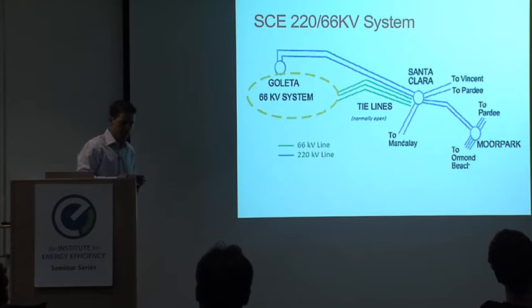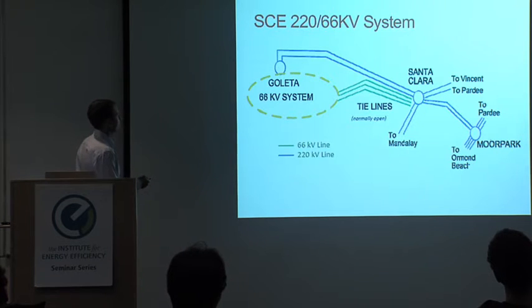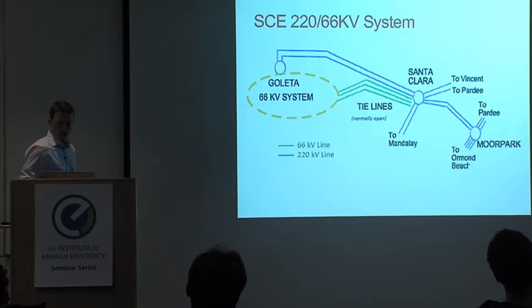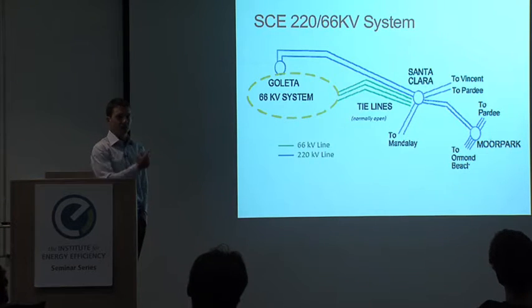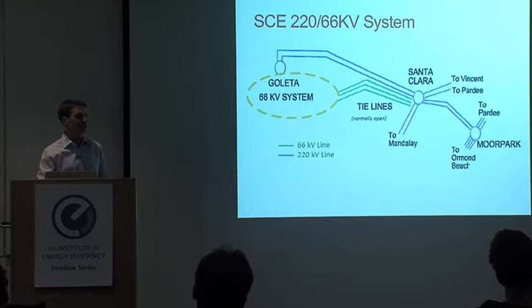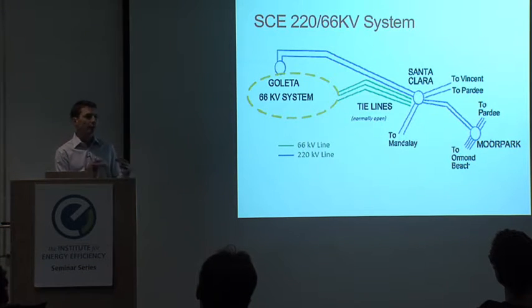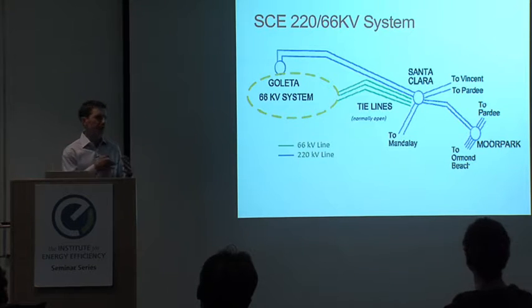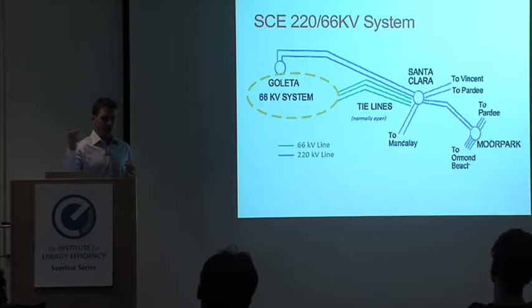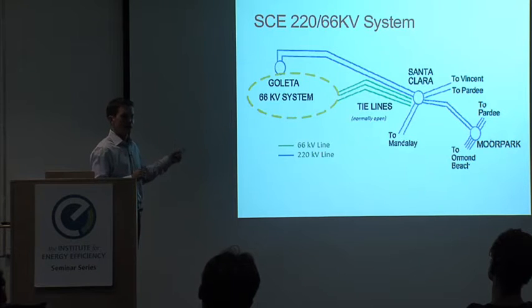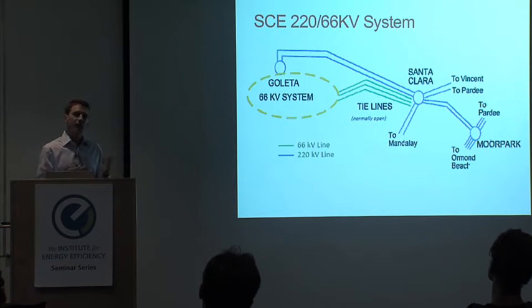This opportunity targets specifically our 66 kV system. This is a conceptual diagram from Edison's GIS layer showing the Santa Clara sub, the 220, and the tie lines. They're looking for 55 megawatts in our area, which is significant—it'll be tough to find siting for that much around here. That's in front of the meter and behind the meter. For us, it would be a behind-the-meter project, something we host and build on campus and use day-to-day. When there's an emergency, Edison gets 4 hours twice a year, and they can dispatch that system to provide power to their 66 kV system if we have another big fire, landslide, or earthquake.